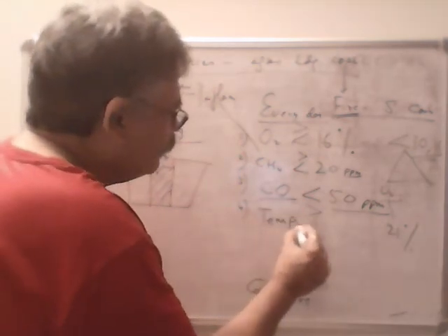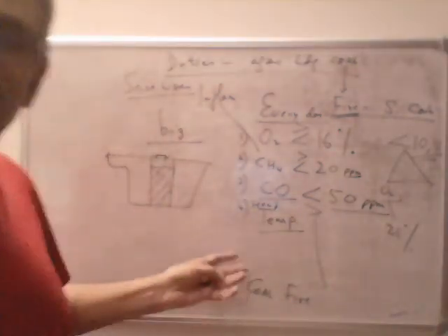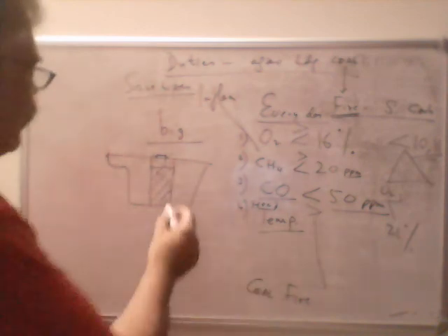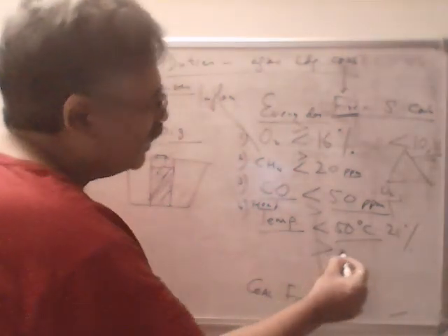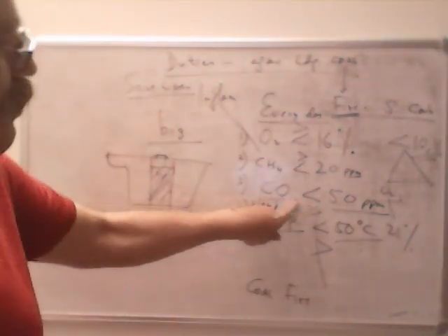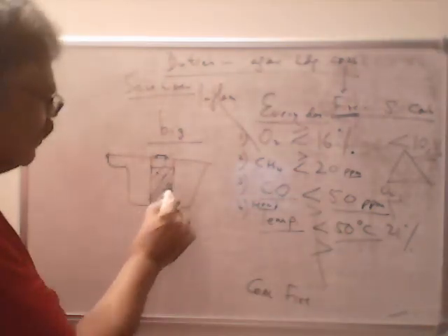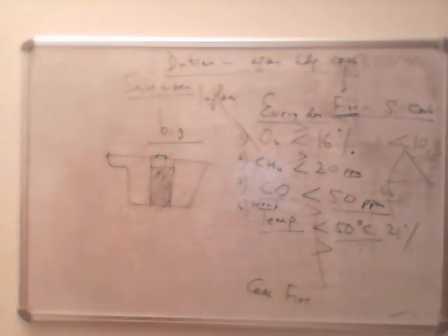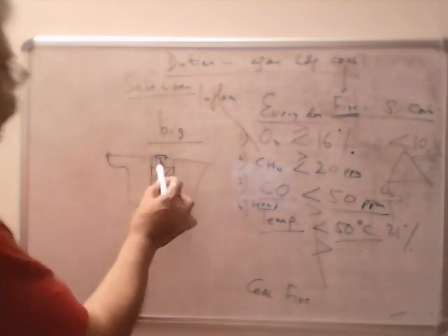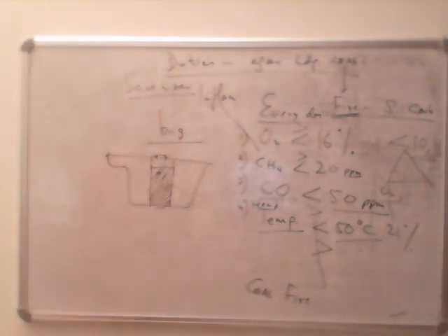The last duty would be to check the temperature of the cargo, hold temperature. Once a day at least. Some companies have twice a day, but once a day at least. Hold temperature should be less than 50 degrees centigrade. That is safe. If it's more than 50, what does it indicate? Same thing. Like CO is more than 50, it indicates that there is a likelihood that fire has already taken place. Again, the same procedure. You can open the hatch, investigate the fire, do firefighting. So that is the 4 jobs you have to do every day after loading coal.